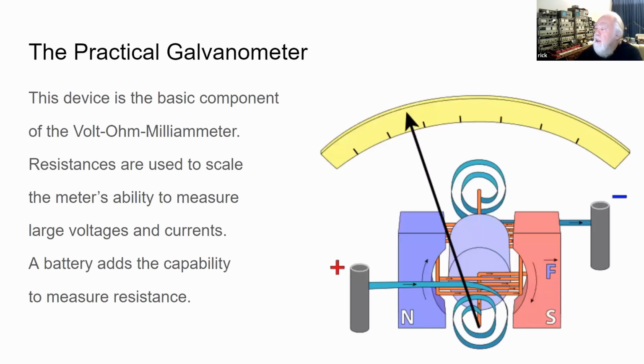Looking at a diagram of how it functions, you see what looks like a motor with fixed field poles, north and south permanent magnets, and an armature with a coil around it. Instead of bearings, we've attached a needle with a pointer, along with a pair of hairsprings shown in blue. The hairsprings serve two purposes: they connect the negative and positive wires to the armature of the meter movement, and they provide resistance to rotation so that at rest the pointer sits all the way to the left, the 0 position on the meter.